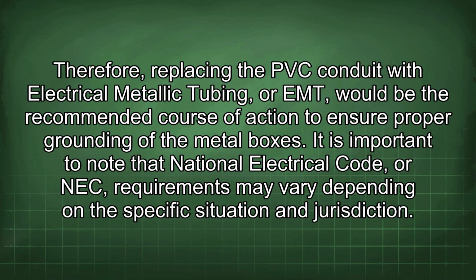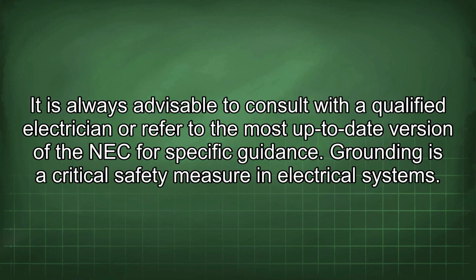Therefore, replacing the PVC conduit with electrical metallic tubing, or EMT, would be the recommended course of action to ensure proper grounding of the metal boxes. It is important to note that National Electrical Code, or NEC, requirements may vary depending on the specific situation and jurisdiction. It is always advisable to consult with a qualified electrician or refer to the most up-to-date version of the NEC for specific guidance. Grounding is a critical safety measure in electrical systems.